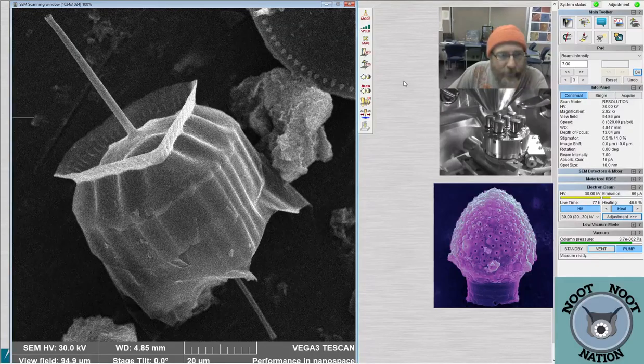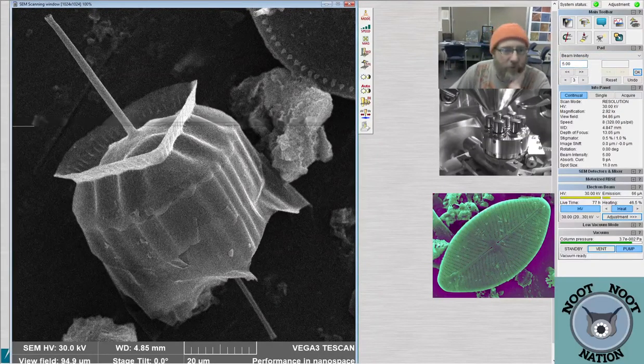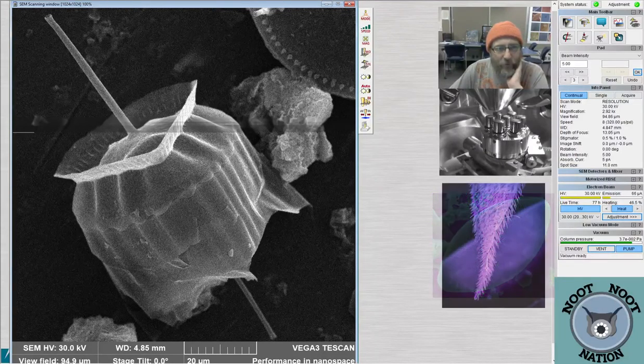So I'm going to set the speed to 8 for this one. And I'm actually going to lower the beam intensity down maybe to 5, so we get a nice high resolution. You can see a little bit more detail as I do that associated with this picture. And then everything's good to go. I'm going to go ahead and start that picture. It's going to take 10 minutes instead of our normal 3 minutes to collect. And then while that's running, I can...